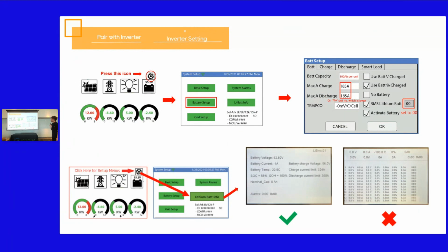Finally, check that the communication is successful by entering the inverter menu bar and viewing the lithium battery info. If you can see battery parameters like voltage, current, and temperature, it means the battery is communicating with the inverter successfully.